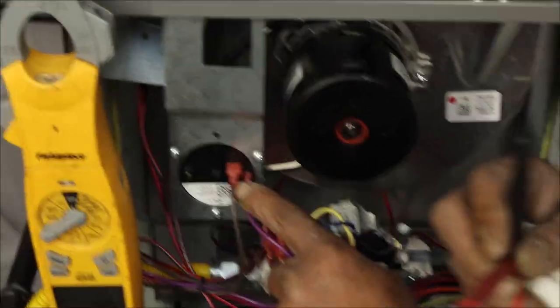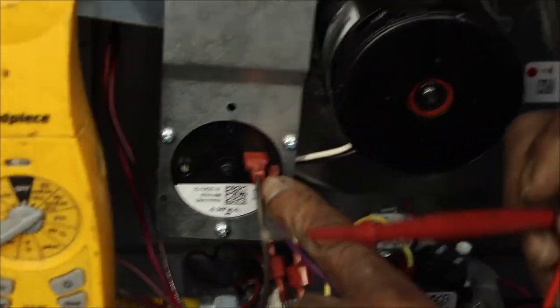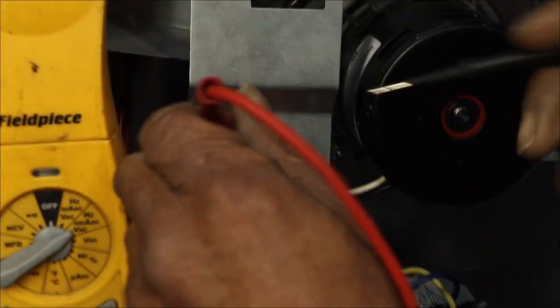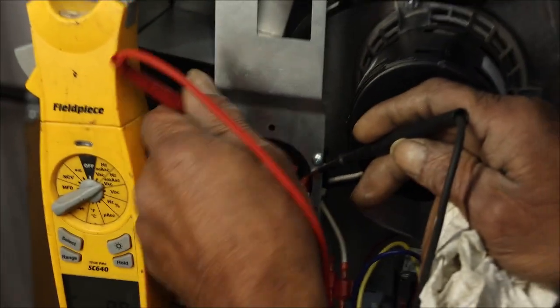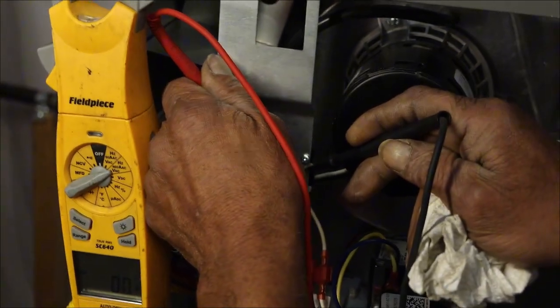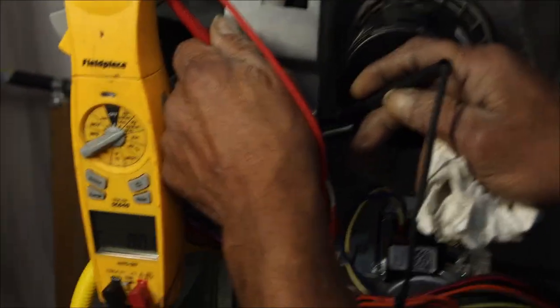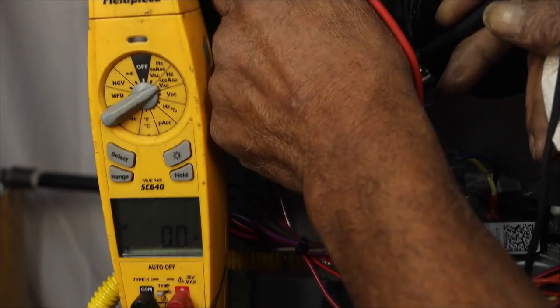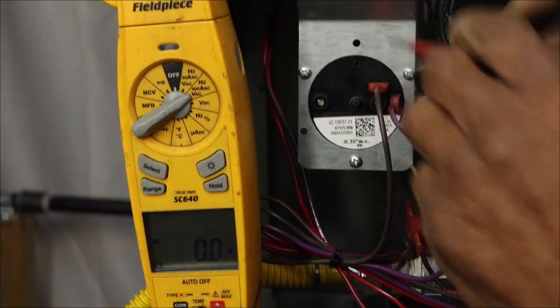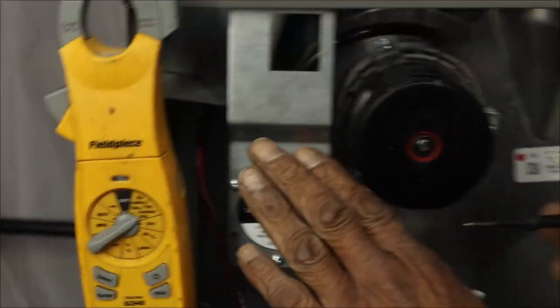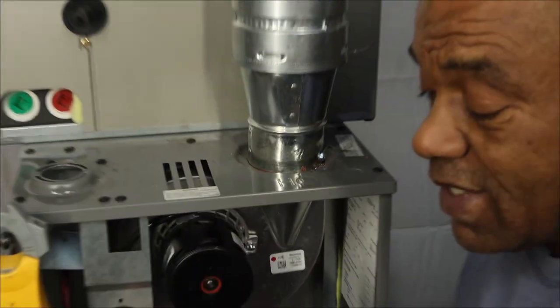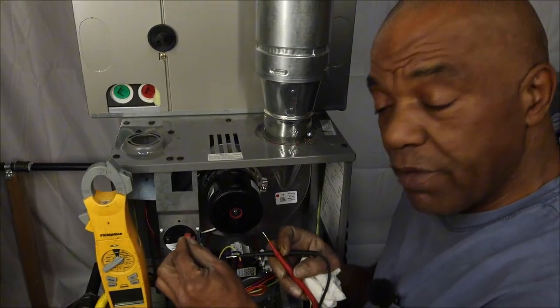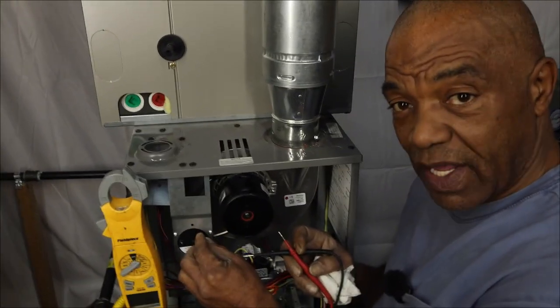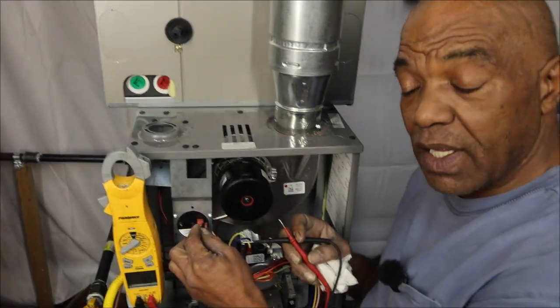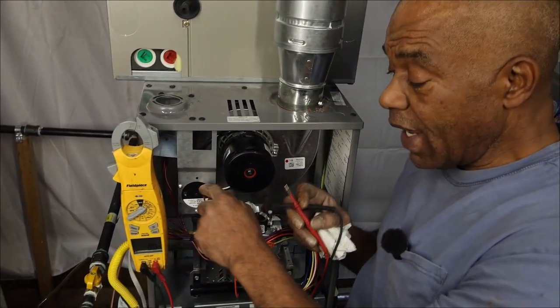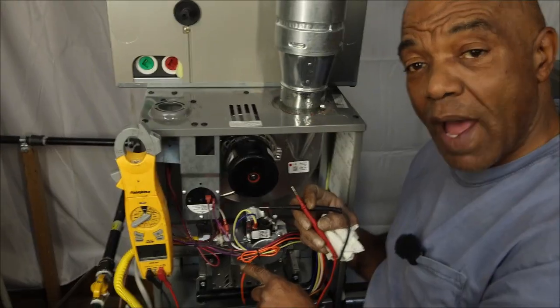So, because it's a switch, I cannot check it with both leads touching it. If I put both leads on it and I look at my amp probe, I see that I have double zeros. Because this is not a device. It does not take 24 volts to activate it. It simply lets power come in and lets that same power go out.